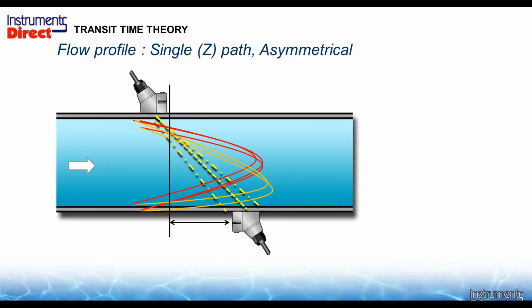Now, should you have an application with a lack of straight run of pipe, the profile distortion may not even be repeatable. So I went out to the job site on Thursday, and I had 1,000 GPM on the pipe, and I had a short run of pipe, and I had to profile the pipe to get a signal. Fine. I come back next Tuesday, and I only have 200 gallons per minute. Well, the flow profile has changed again because of the lack of straight run of pipe. I may have to move the sensor again. So varying flow rates will change where the metering point could be if you have a short run of pipe application. Now, spot checking, which is what you're going to do most of the time with your PT878, is not so much of a problem. If you're going to leave it there for a day, week, or month for a flow survey, that could be an issue.